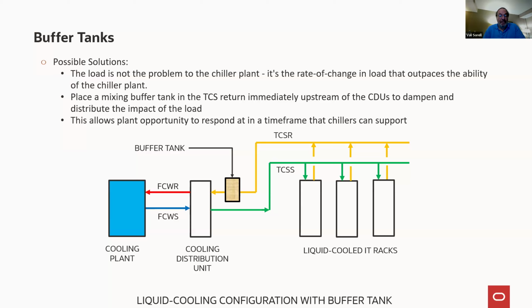If we don't address it, we will inadvertently be creating very unstable performance for the infrastructure, and potentially, depending on how the workload goes through the IT racks, we could be setting ourselves up to actually lose our chiller plant and then have to do a restart. And then all of the servers, of course, need to shut down and wait for things to return to normal again. So it's a reality. We do need to do it. So the idea is to put a buffer tank here.